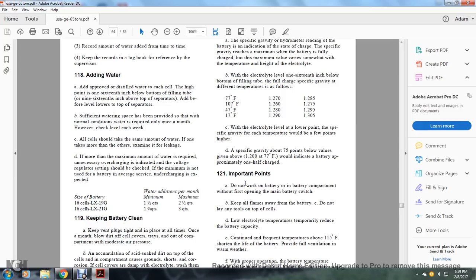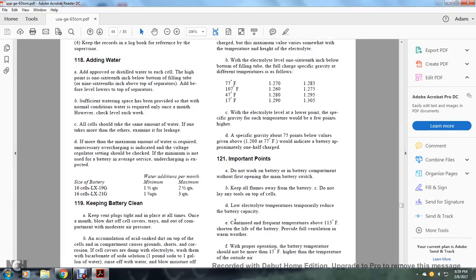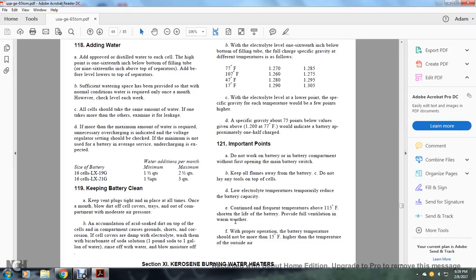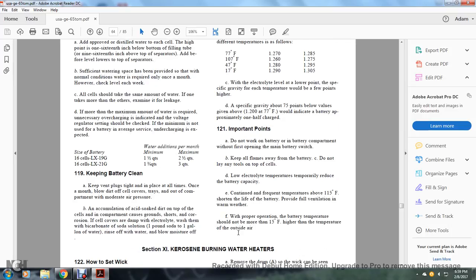Important points: Do not work on the battery or battery compartment without first opening the main battery switch. Keep all flames away from the battery. Do not lay any tools on top of the cells. Low electrolyte temperatures temporarily reduce battery capacity. Continued frequent temperatures above 115 degrees shorten the life of the battery. Provide full ventilation in warm weather. With proper operation, battery temperature should not be more than 15 degrees Fahrenheit higher than the temperature of the outside air.